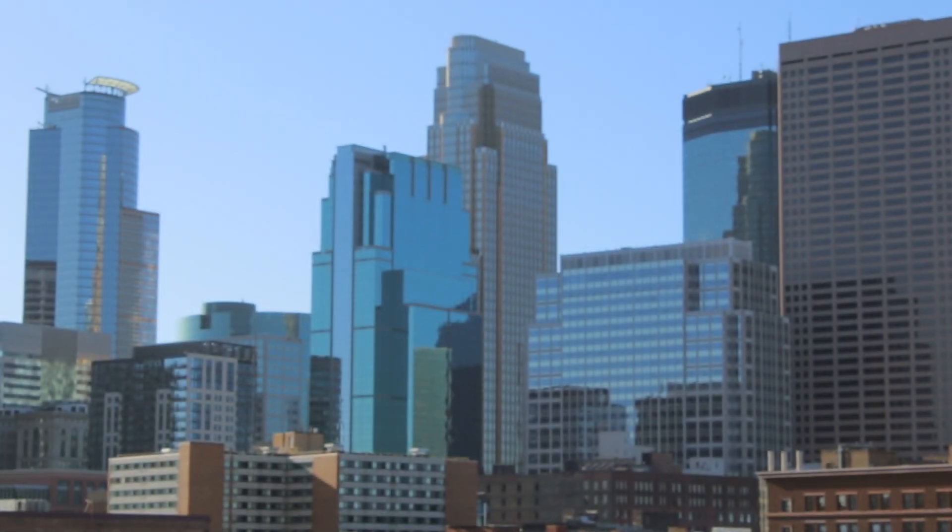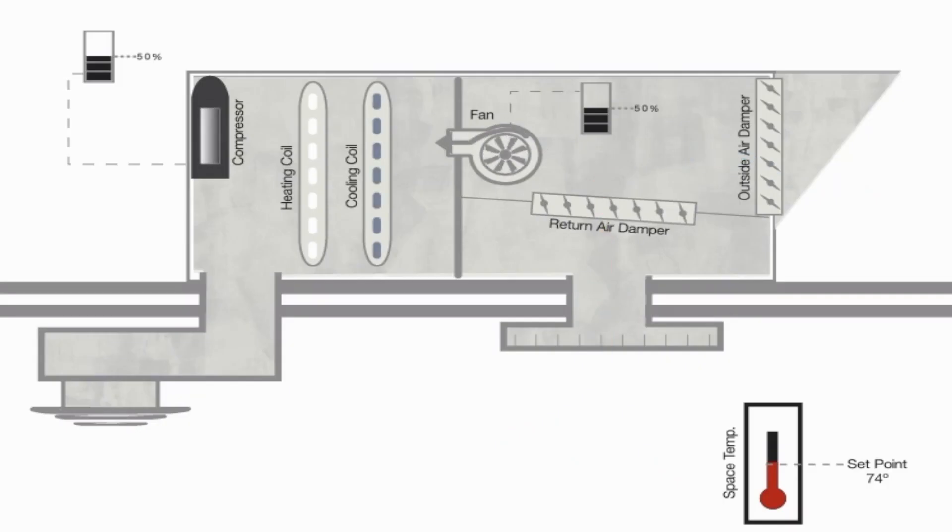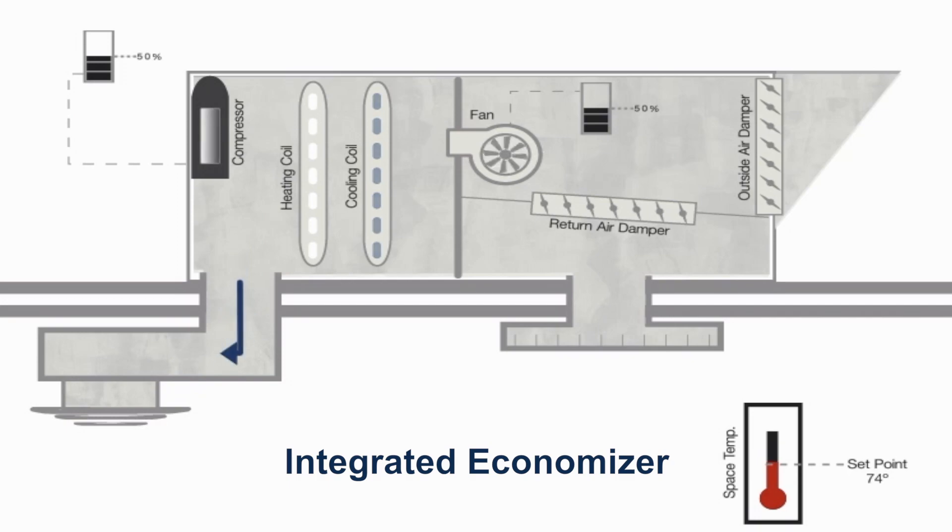Since most businesses produce a lot of excess heat, most RTUs today can seamlessly combine free cooling with AC as needed in what's known as an integrated economizer. An integrated economizer utilizes control logic already built into the economizer to determine if you can use outside air plus the air conditioning to cool, outside air alone, or just simply air conditioning when the outdoor temperatures aren't appropriate.